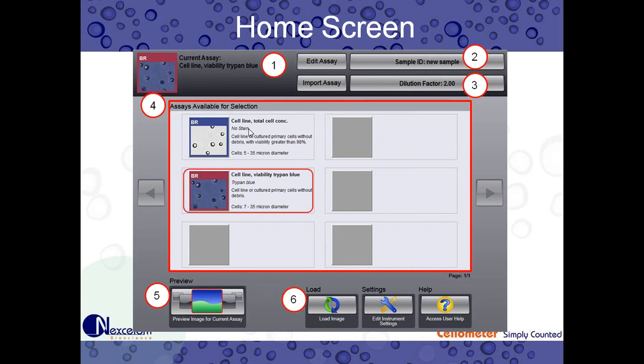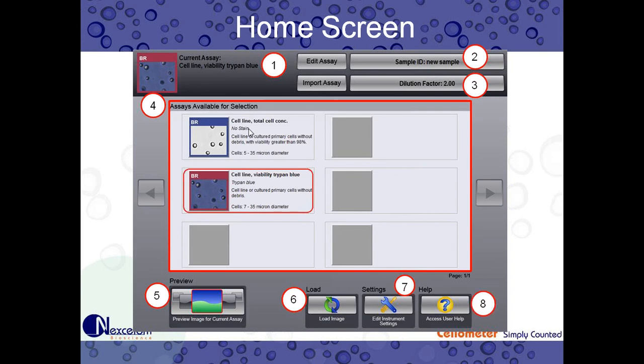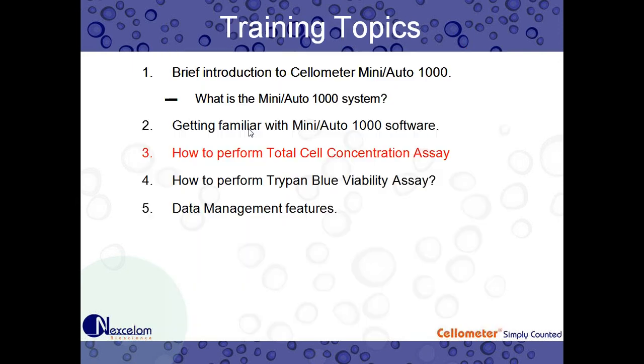Number six, if your Mini, if you have saved images on your Mini computer or if you have a USB or network connection on your Auto 1000, we can load previously saved images and reanalyze those for the cell concentration, size analysis, and viability. Settings takes us to our counting options so users can adjust the speed of counting or adjust the data or image saving. And then lastly, we have our help button. This is what users can select to access our electronic copies and manual or if your Auto 1000 or Mini has network access or internet access, you can find our online help tutorials, FAQs, videos, and a support webpage.